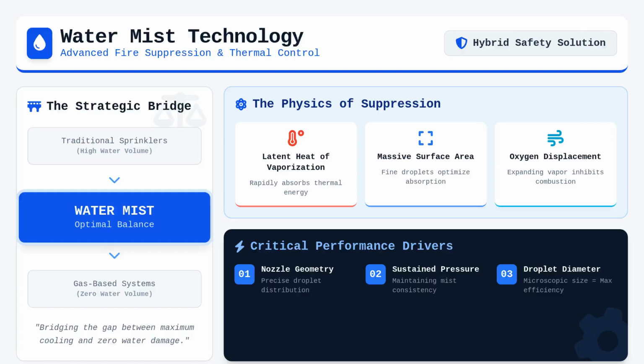Because mist systems operate at much lower water volumes than traditional sprinklers, they provide significant benefits in environments where sensitive water damage is a concern, such as archives or machinery spaces. Mastering these systems requires an intimate knowledge of how droplet diameter influences effectiveness, as the physics of energy absorption depends entirely on creating an environment that inhibits combustion at the microscopic level.